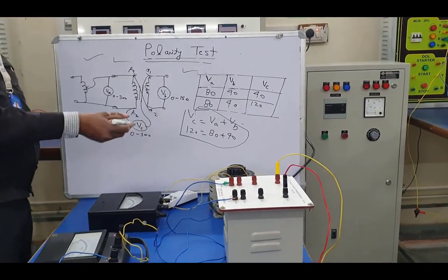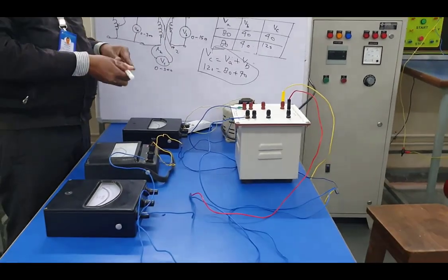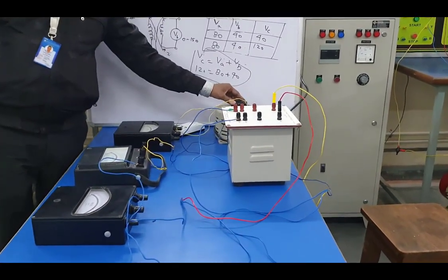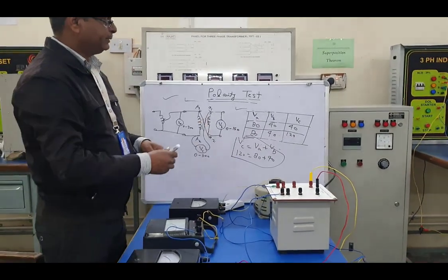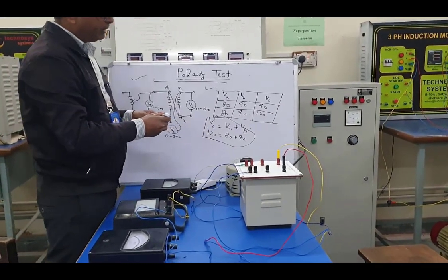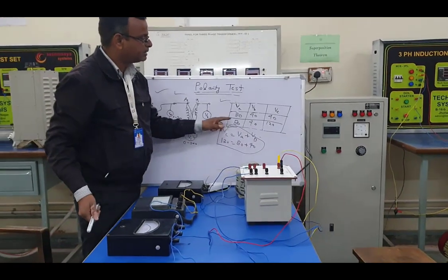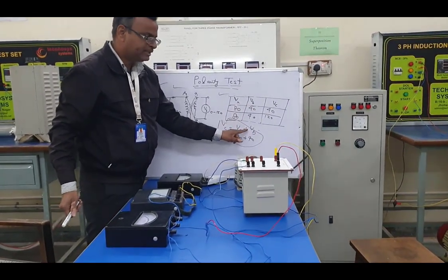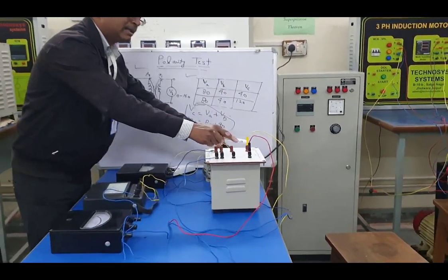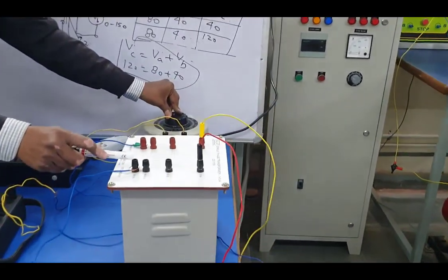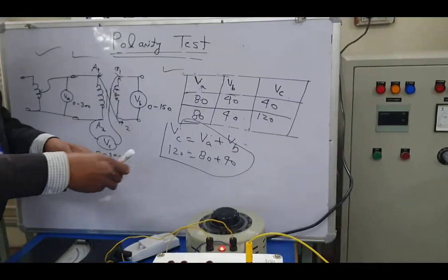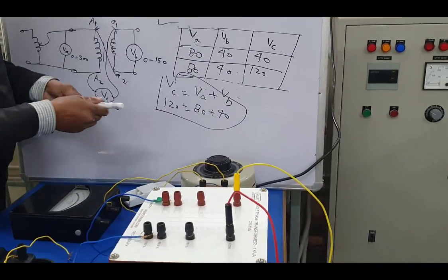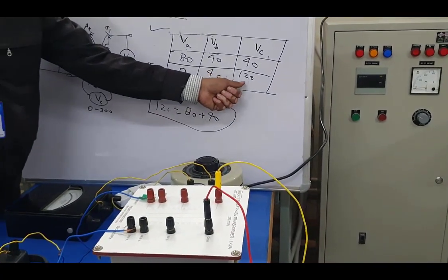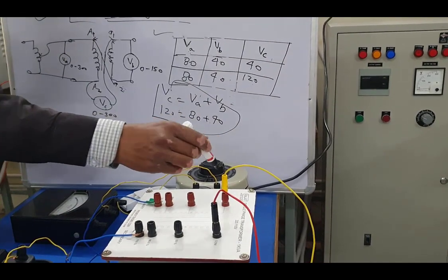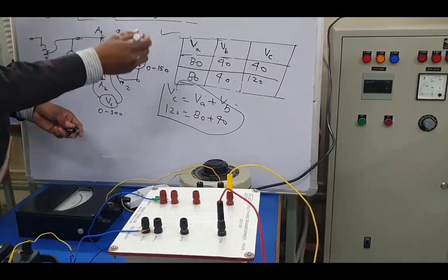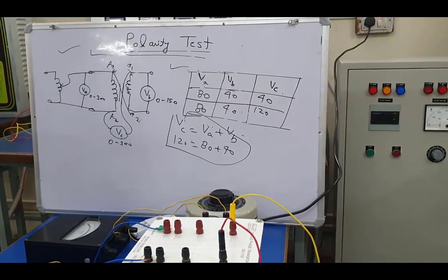These two types of polarity exist in the transformer. One is the additive polarity, the second is the subtractive polarity. Basically, the conclusion is that in the first case we get the subtractive polarity, VA minus VB. It means the same terminals are connected, plus to plus and minus to minus. But in the second case, we just interchange the terminals and we get the additive polarity. So in that case the plus terminal connects to the minus. So these two types of polarity we have to find in the polarity test.